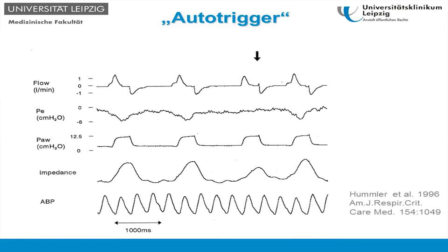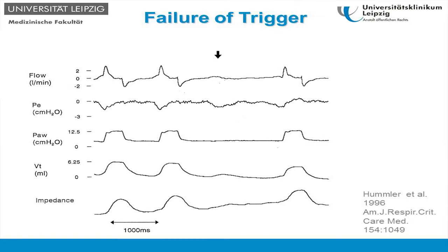However, we can also get auto-trigger. This is again the esophageal pressure reading, and we clearly see that the patient didn't want a breath here, but anyway, he got one because some movement artifacts triggered the machine, and the infant got a breath. So this is auto-trigger, which can be fixed by increasing the trigger threshold, but then the triggering will get slower. So it's sometimes a difficult task to find the correct trigger threshold for optimal interaction.